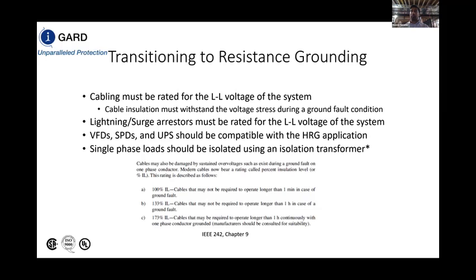When it comes to VFDs, surge protection devices, and UPSs, we have to ensure that they're compatible with the HRG system. Sometimes VFDs may have a direct connection between their conductors and ground, either before the rectifier circuit or after the rectifier circuit on the DC link. And as a result, that may bypass our resistor and no longer allow us to limit fault current to a specific value, since the ground fault will take that path through the VFD back to the ground fault point.